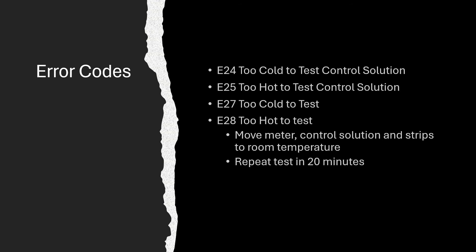And then there's some error codes related to extreme temperatures. E24, it's too cold to test control solution. E25, too hot to test control solution. E27 is too cold to test.